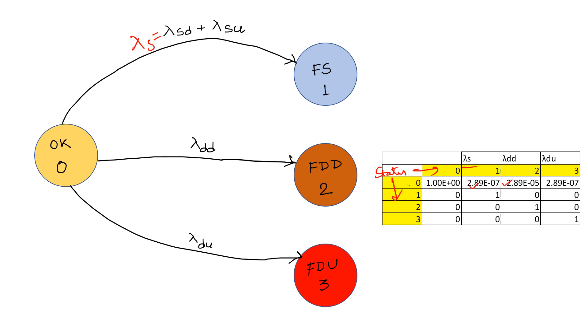The transition from state 0 to state 3 is given by lambda_DU. These states are absorbing — no repair is possible, so items cannot transition from fail safe back to OK, or hop between fail states. Therefore the probabilities of going from state 1, 2, or 3 back to state 0, or between states 1, 2, and 3, are all zero.